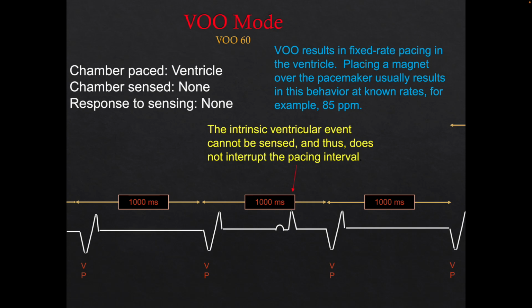And I've gotten those calls. The patient said, we heard DDD 60, but their own rate is 80. They're not going to pace because it's set at 60, and let's just say 120 is their upper rate. So they may not pace. It's all about timing of their own rhythm with the device settings.